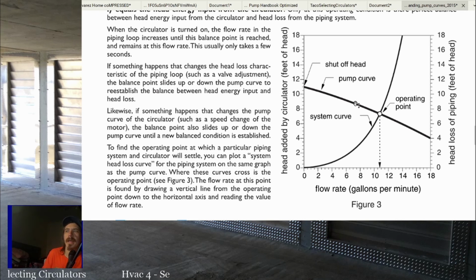So you've got that. And then down here, basically, if you get past that on this end, then the pump's not working against any pressure at all. So it's basically just like having the pump run open on the end. It's not going to be very efficient. Generally, your efficiency is in the middle of your pump curve. Too far this way, and the motor is just spinning too fast and not doing anything. And up here, it's working too hard.